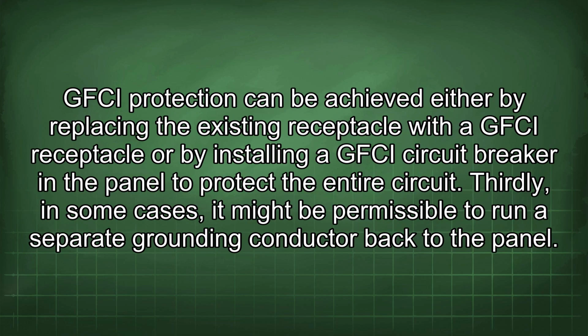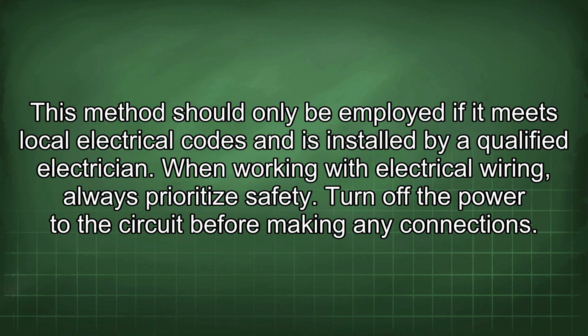GFCI protection can be achieved either by replacing the existing receptacle with a GFCI receptacle or by installing a GFCI circuit breaker in the panel to protect the entire circuit. Thirdly, in some cases, it might be permissible to run a separate grounding conductor back to the panel. This method should only be employed if it meets local electrical codes and is installed by a qualified electrician.